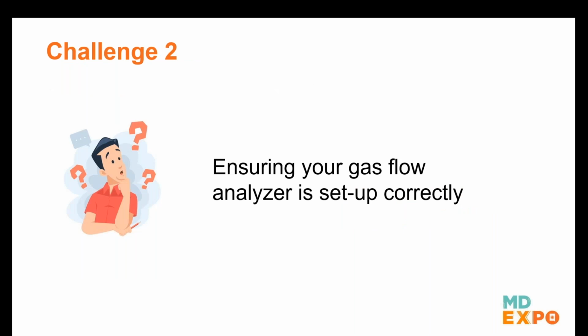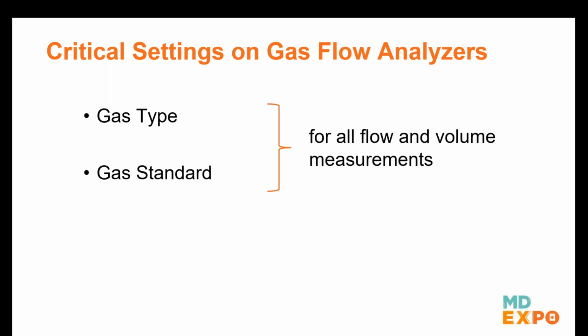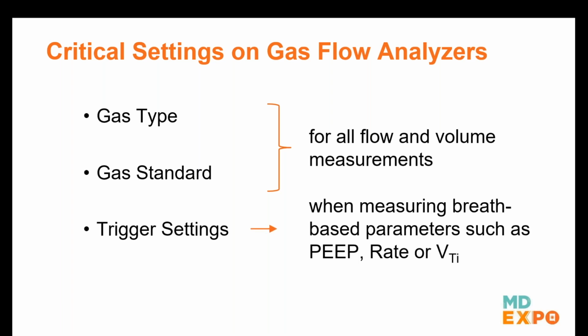Okay. The next thing that we want to talk about is a challenge that we face all the time, and that's ensuring that whatever gas flow analyzer we're using, that it's set up correctly. There's a lot of kind of science to follow, and we won't get too far into it. But we're going to talk about gas type. We're going to talk about gas standards. We're going to talk a little bit how those are used to do volume and flow measurements. We're going to talk about trigger settings. Trigger settings are used anytime that you want to do a breath-based parameter, things like PEEP, rate, tidal volumes, things like that. And the fourth thing that we want to talk about with regard to settings is the measurement parameters themselves.